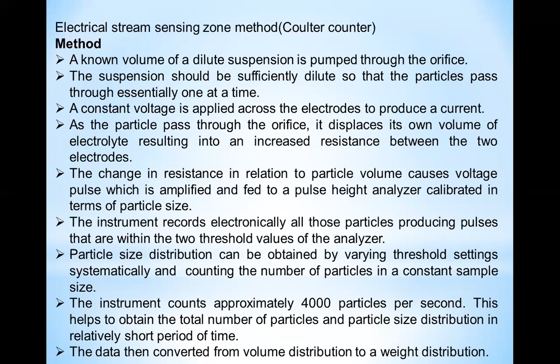Particle size distribution can be obtained by varying threshold settings systematically and counting the numbers of particles in a constant sample size. The instrument counts approximately 4,000 particles per second. This helps to obtain the total number of particles and particle size distribution in a relatively short period of time. The data is then converted from volume distribution to a weight distribution.